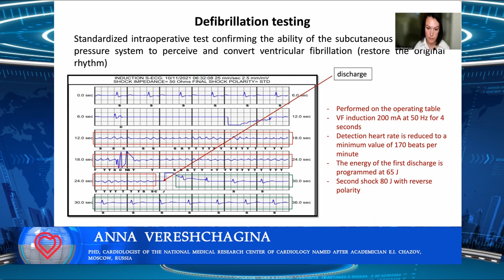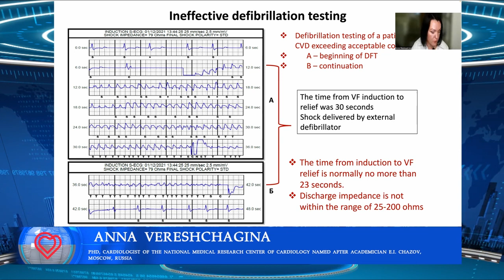If ventricular arrhythmia is not recognized by the device, or if the discharge delivered by the subcutaneous device does not result in conversion to the original rhythm, such therapy is deemed ineffective with the subcutaneous ICD system, requiring external defibrillation, as shown in the electrogram. In case of ineffective defibrillation testing, repositioning of the subcutaneous lead or pulse generator may be necessary. The time from induction to termination of VF should normally not exceed 23 seconds, and the discharge impedance should remain within the range of 25 to 100 ohms.